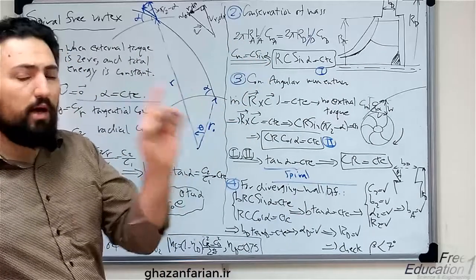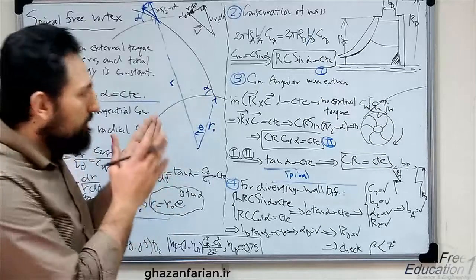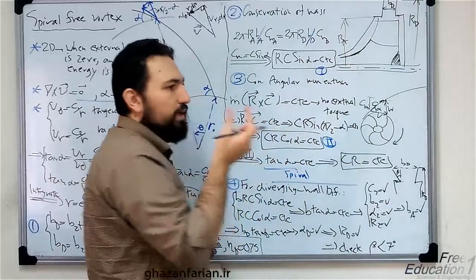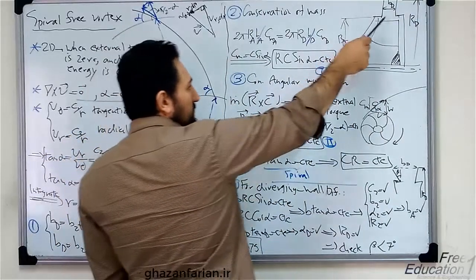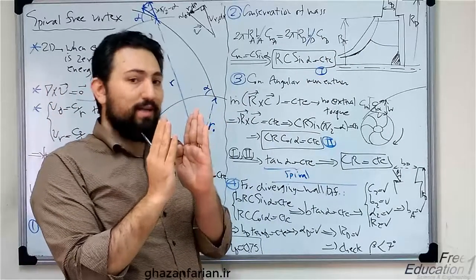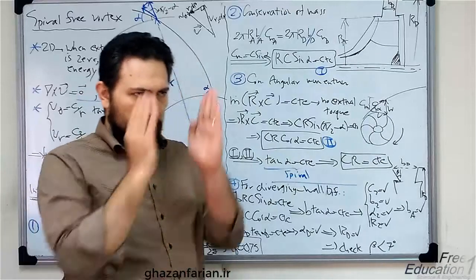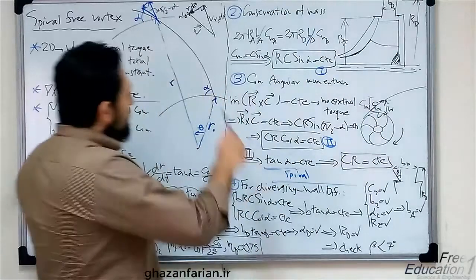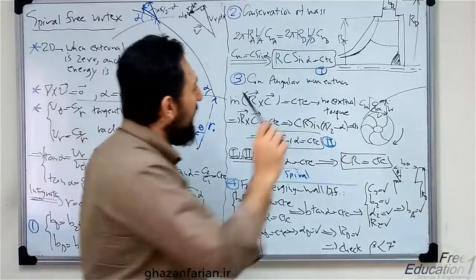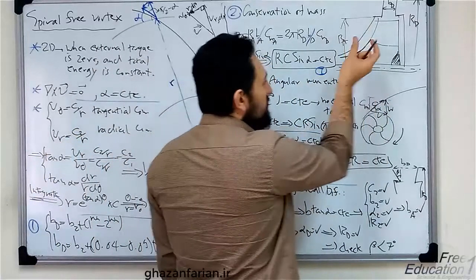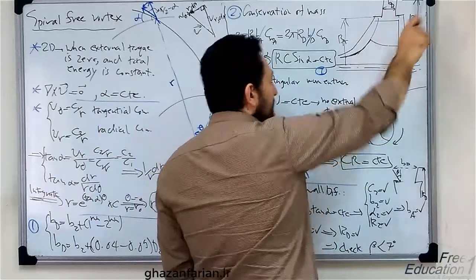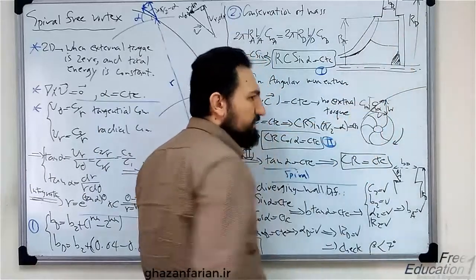If I want to design a diffuser for a pump, I have to compute the magnitude of different geometrical constants. This type of diffuser is called the parallel wall diffuser — it means we have two parallel walls at the outlet of the impeller, which is axisymmetric. We have to find a relation to compute the magnitude of B sub D, which is the distance between the two walls of the diffuser, and also the radius of the outlet of the diffuser, shown by R sub D.